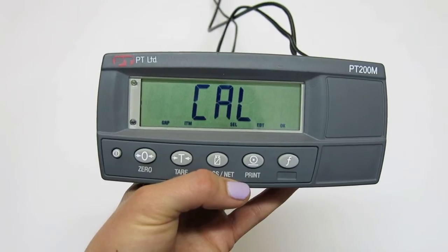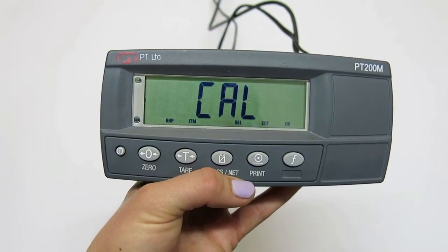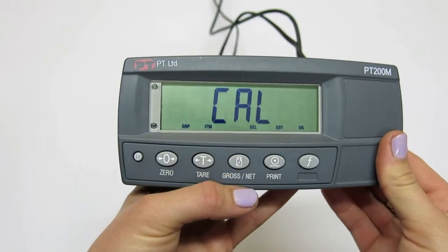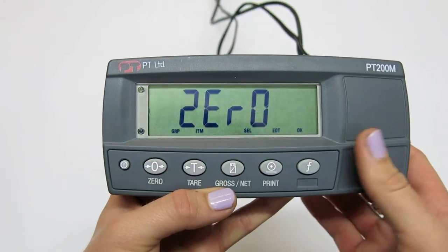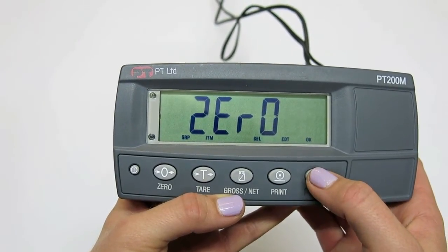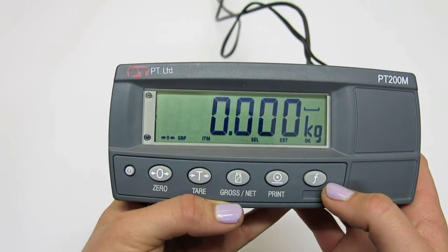For regular calibration, first find the zero option in the calibration menu and press OK or the F button to select. Ensure there is no excess weight on the scale and press OK again to set this as the new zero offset.